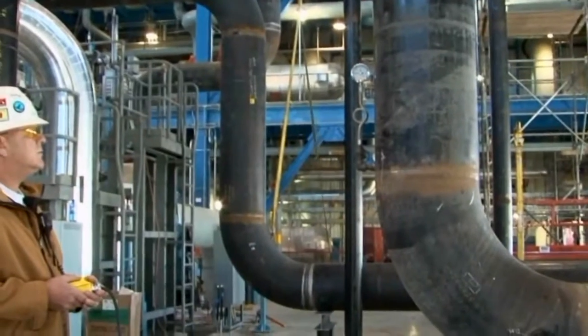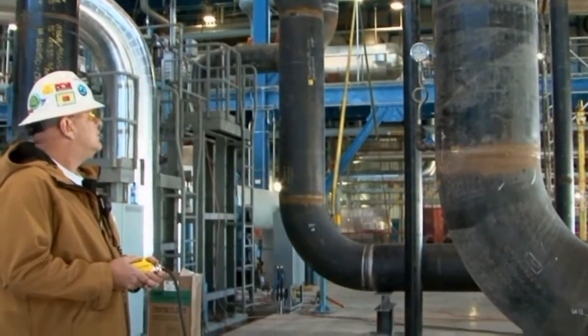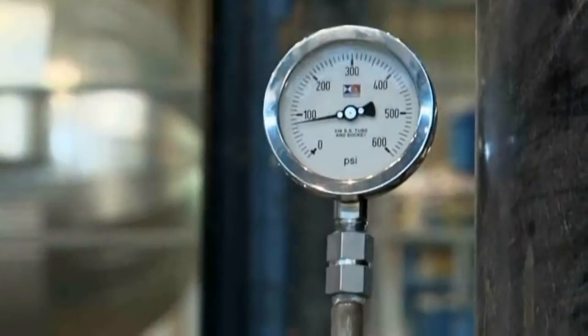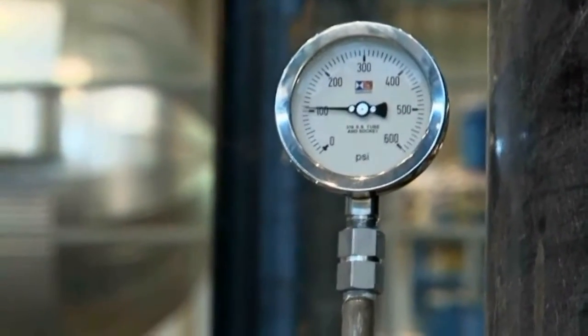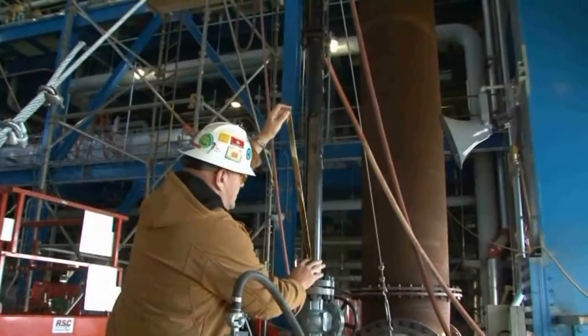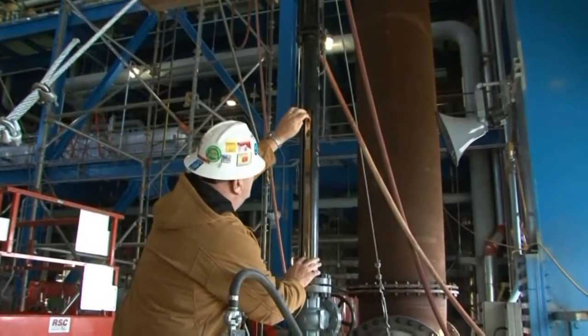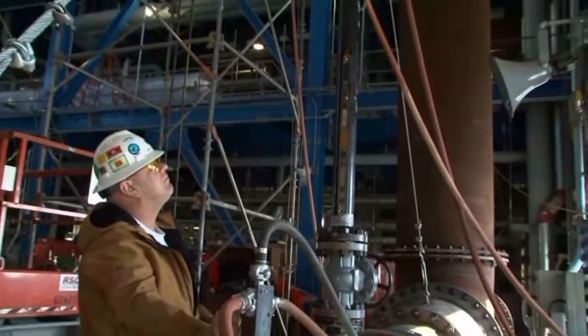You don't get to where there's no debris, but you get to where, it's a percentage, I'd say like 90%. You know that you're 90% clean. If they didn't blow out the pipes on a power plant, debris like welding slag would damage the turbine. That would be a major disaster. Well, you get a lot of erosion. You might even get, if it's a big piece of debris, significant blade damage or breakage. Every so often during air blows, a brass target is inserted into the pipes.